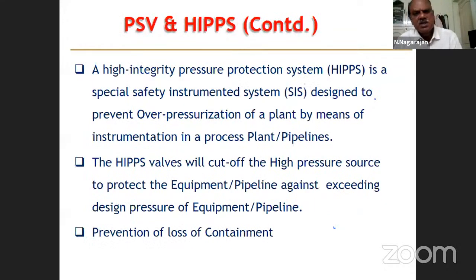High integrity pressure protection system is nothing but a highly reliable safety instrumented system. It comes under safety instrumented system. It is designed to prevent over pressurization of a plant. This usually, as I said earlier, comes at the entry point of the plant. Okay, suppose we get hydrocarbons, crude oil or gas from the wells. So when the well control is lost, and suddenly the entire stream coming into the plant is at well reservoir pressure, which may be 100 bar, but your plant is designed for 25 bar, let us say.